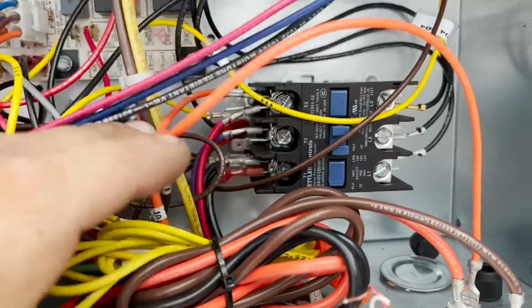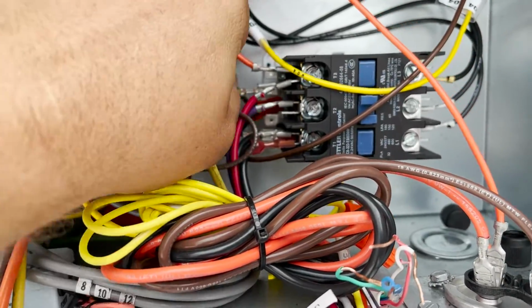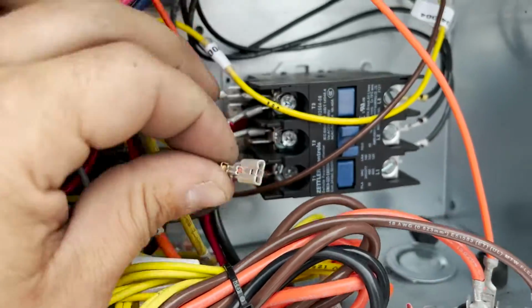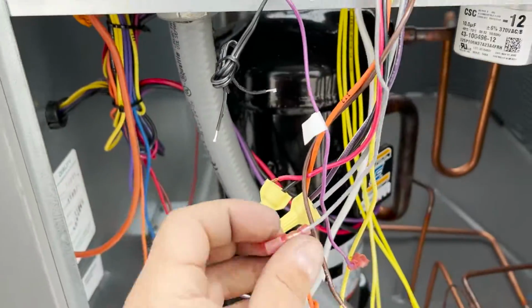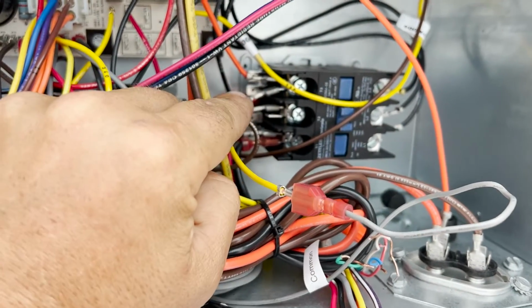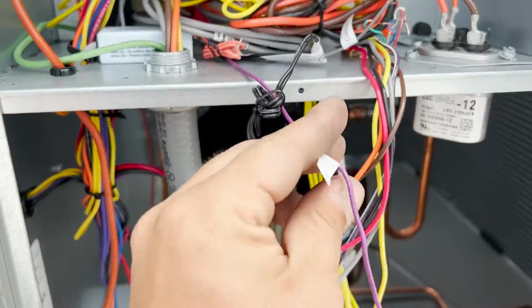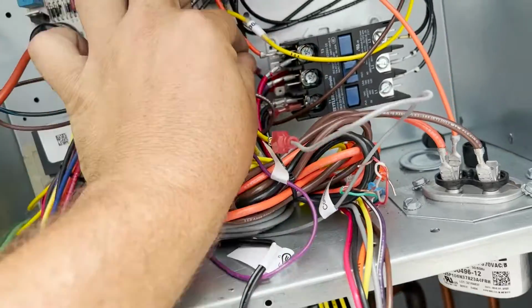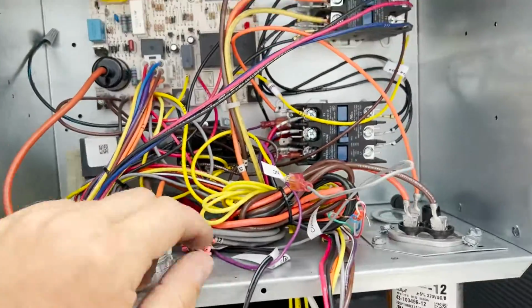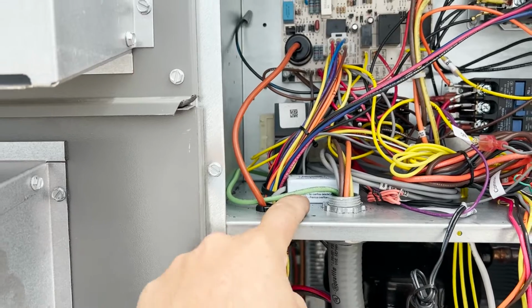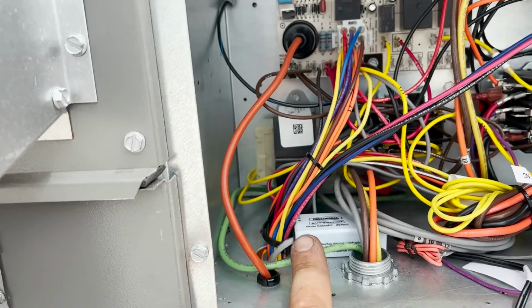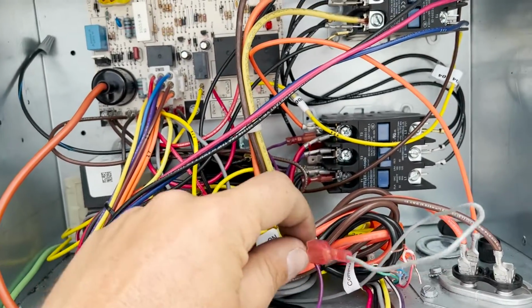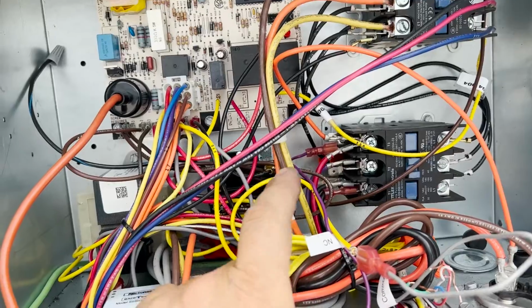So what we want to do is to turn off the compressor if the pan floods, right? So this back here is our compressor, 24 volt. We're gonna take on that and connect it to our common. Sorry, I can't do this one-handed, right? So now, instead of going directly to the contactor, it's gonna go through this float switch to the normally closed contact. We're gonna put that right back where our low voltage was. So now our compressor is broken through the float switch. If this float switch fails or it needs to be removed from the circuit for whatever reason, this can go right back to there and this unit will be operating no problem.